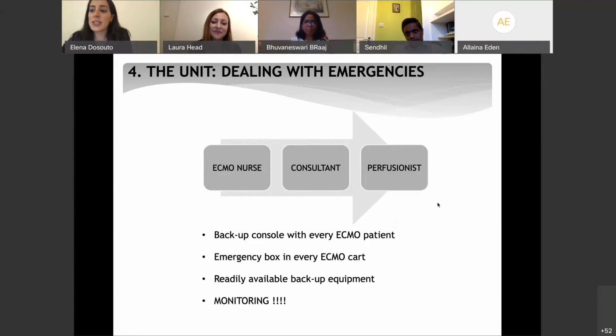In case of emergencies, we have loads of backup equipment readily available. So we have a prime circuit in the unit, we have a backup console with every patient, and we have an emergency box by the bedside if something happens. So yeah. However, the key for preventing accidents is monitoring, because most of these problems that can happen are completely preventable. For example, we know an oxygenator is starting to clot because we can look at the trend within the shift. So we can look at the pressure pattern over the shift and we know the direction it's going.